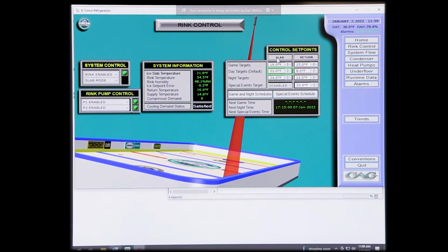In control set points, you have the ability in slab to run game targets, day, which is default, or night targets. If you're not using the rink, you may as well save a lot of energy. Run it up a couple of degrees. Most customers, I tell them the max you really want to do that is about 3 degrees. Remember that your alarm target is 28. If you choose to do 28, you've got to remember that by the time the system cuts on, you may hit 28.5. That will generate an alarm. There are other rinks that do run these systems that high. We've had to inhibit alarms, and I mean, they run the borderline of, I can't believe they have good hard ice, but they do somehow.